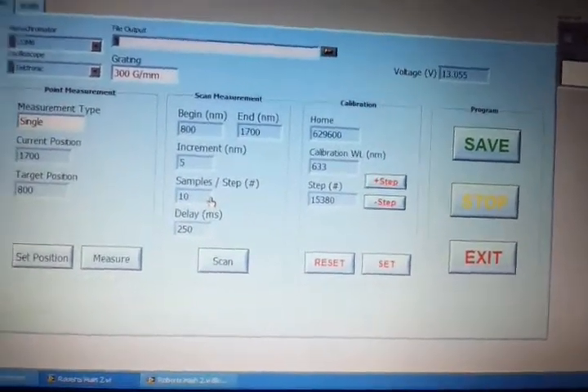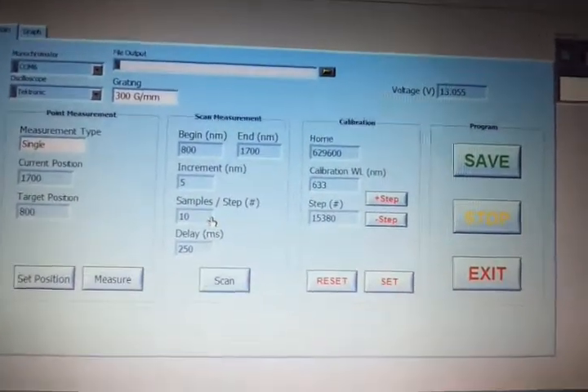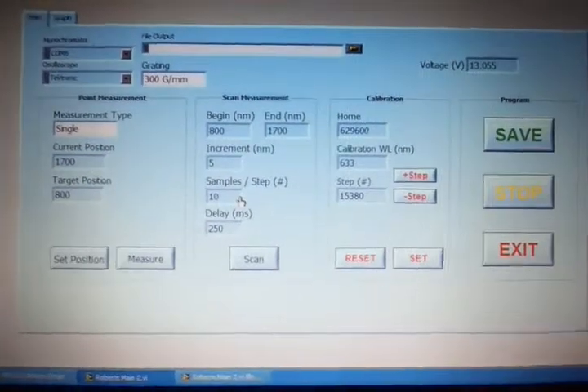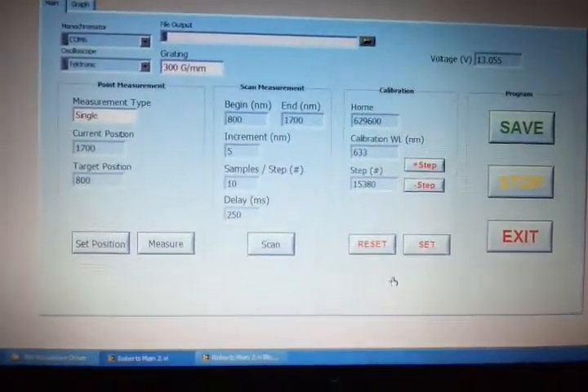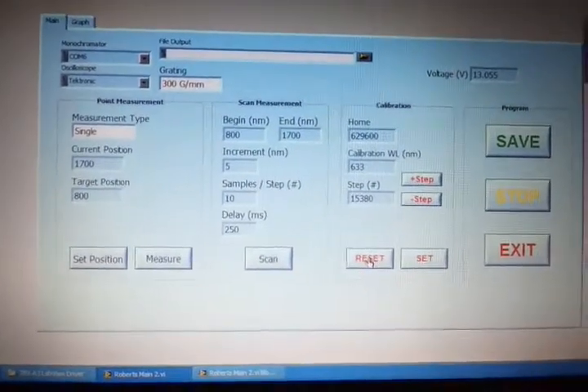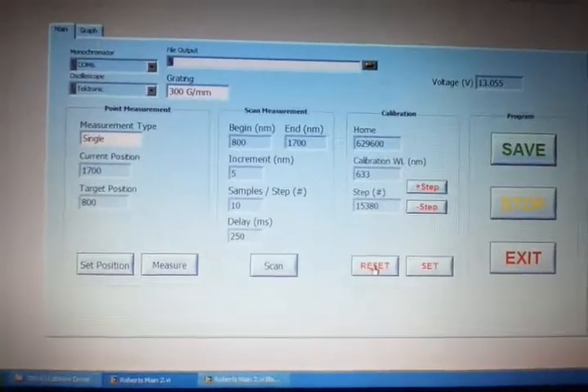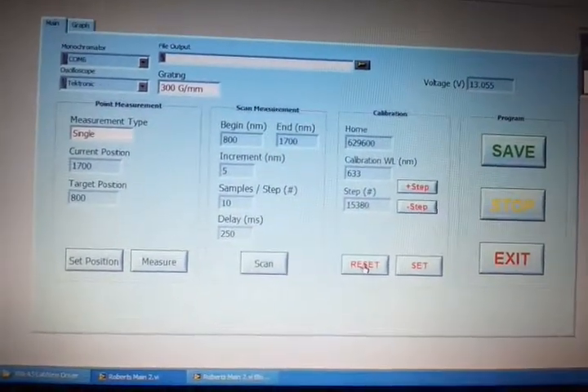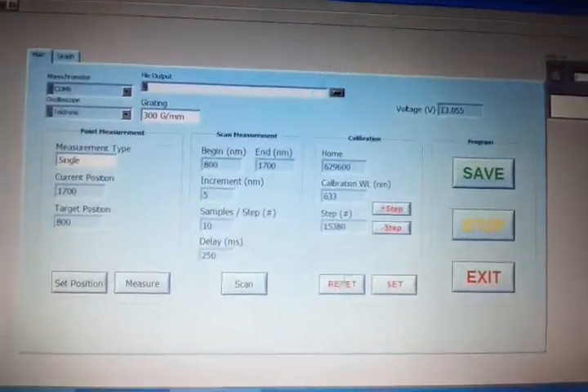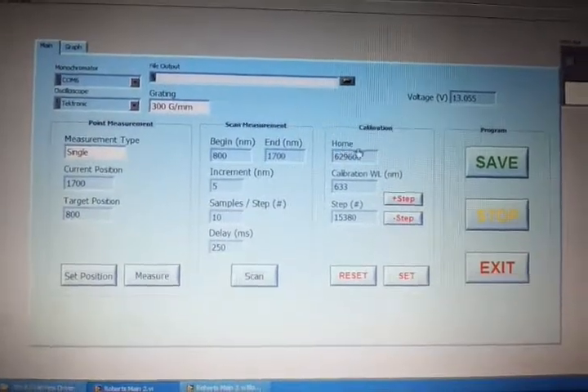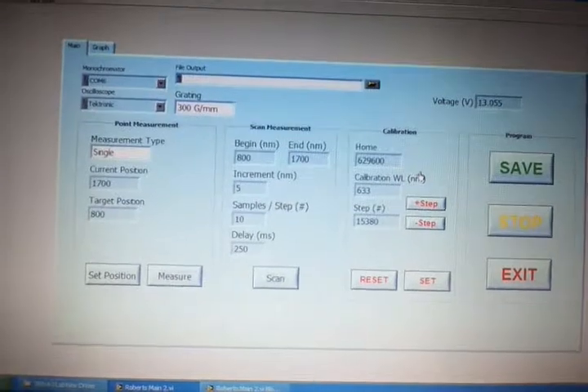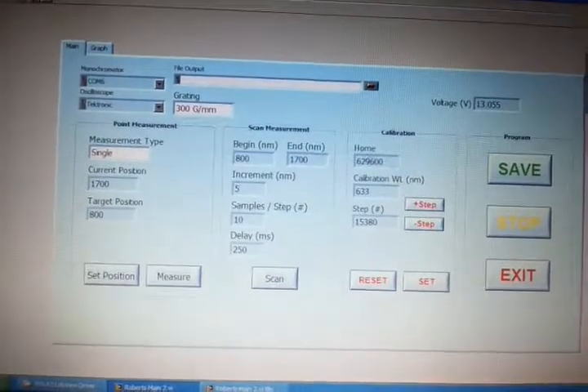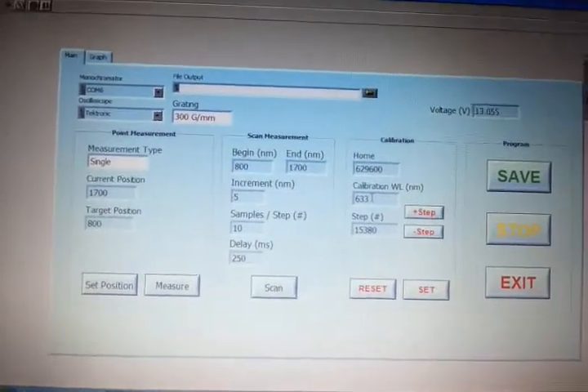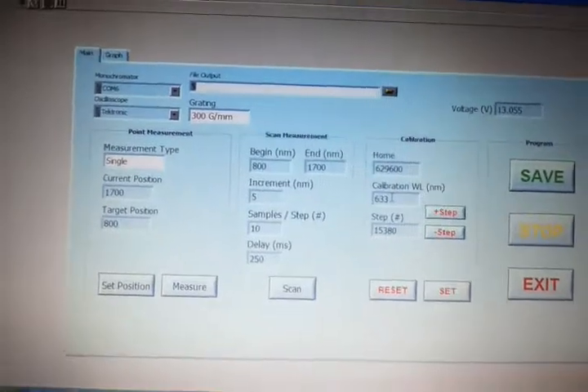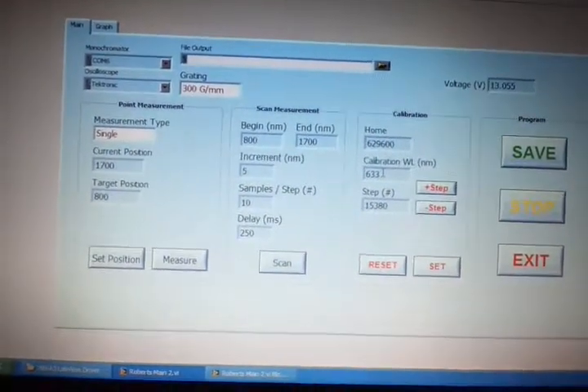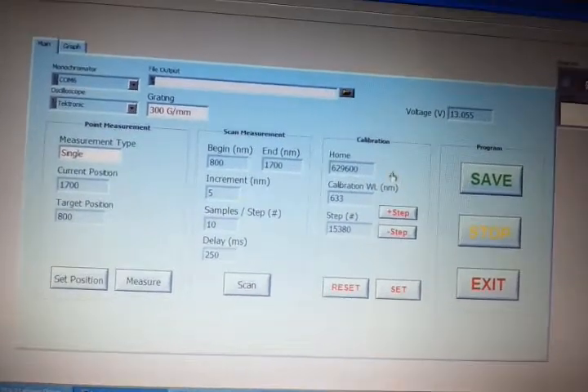What has been done in the past so far is to just do single calibration with a HeNe laser at 633 nanometers. The first thing you do is you click reset. What that does is it moves the grating to the lowest position, the lowest counter that it can, which is into the UV range, and then moves it back up to whatever home count number this is set to. Once it gets there, it waits for you to decide whether that counter number here corresponds with the wavelength from your input reference, which in this case is a 633 or 632.8 HeNe laser, and you determine that based on the voltage here.